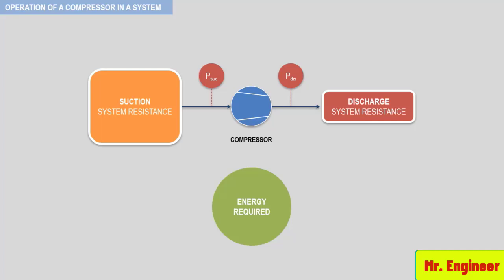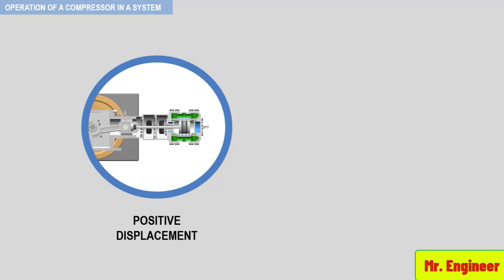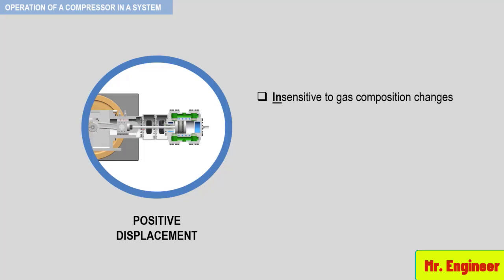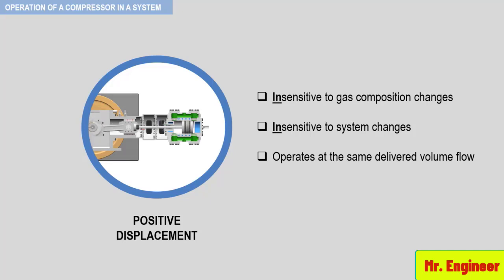If we review the previous section and examine the operation of both positive displacement and dynamic compressors in a simple system, two important facts become evident. A positive displacement compressor, since it increases the energy of the gas by operating on the gas in a confined space, will always increase the energy provided sufficient power is available. Therefore, a positive displacement compressor will be relatively insensitive to gas composition changes. In addition, since it has variable head capability, it will be relatively insensitive to system changes. As a result, a positive displacement compressor will operate at approximately the same delivered volume flow, regardless of system resistance or gas composition.